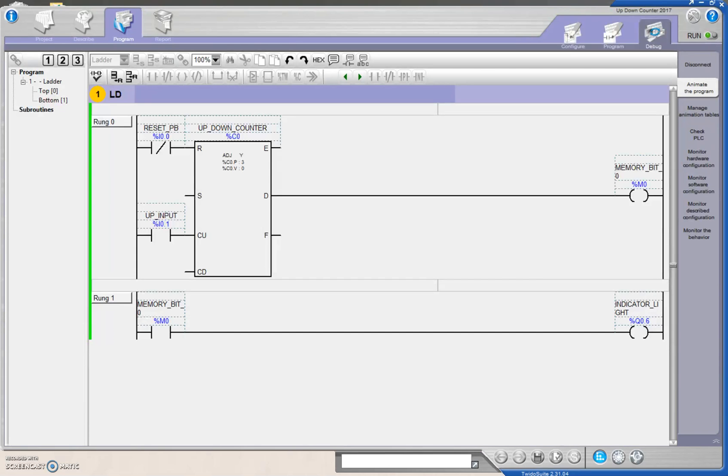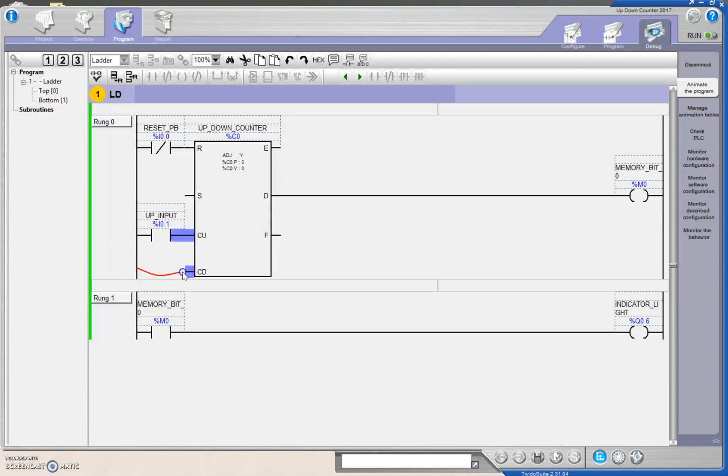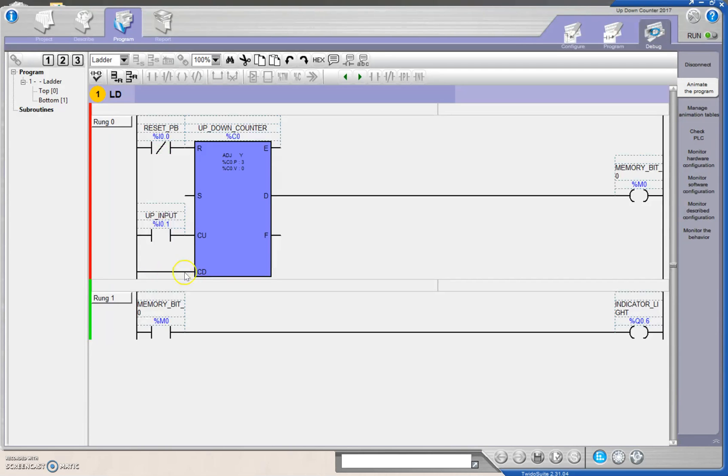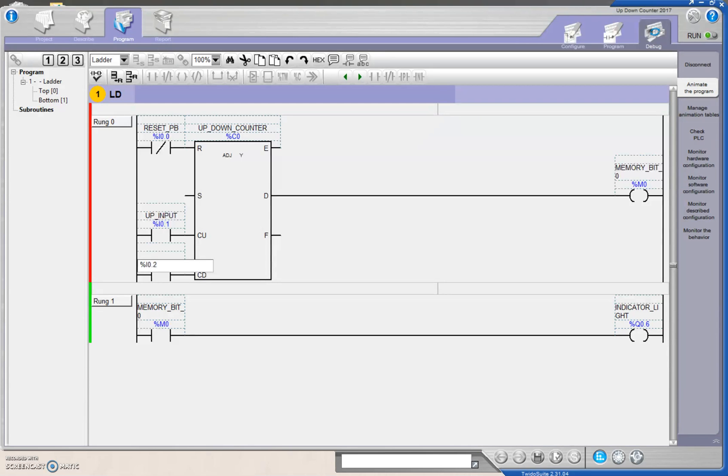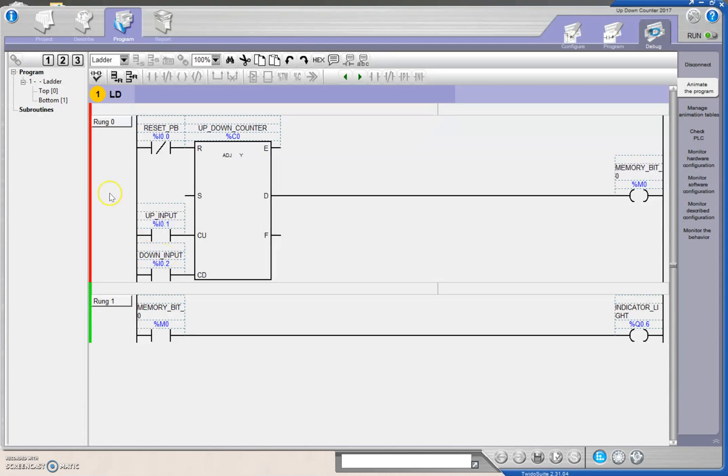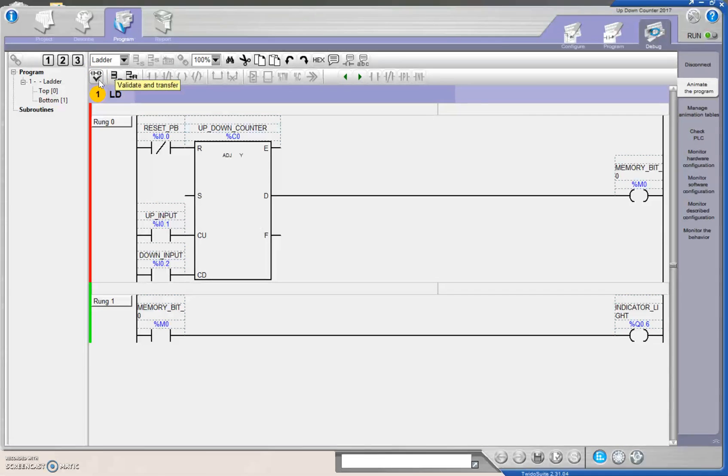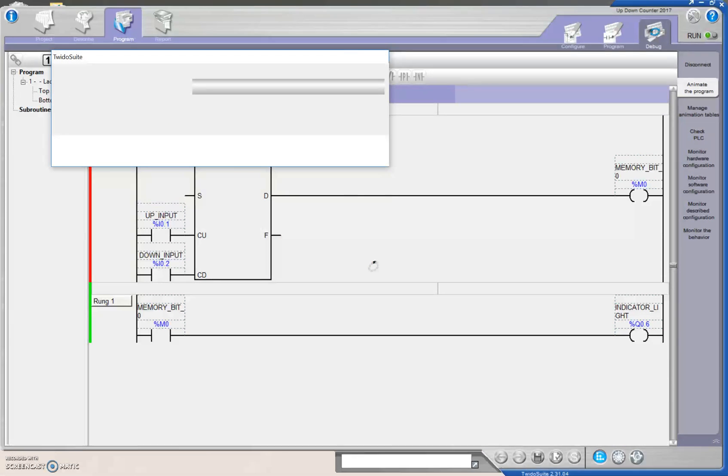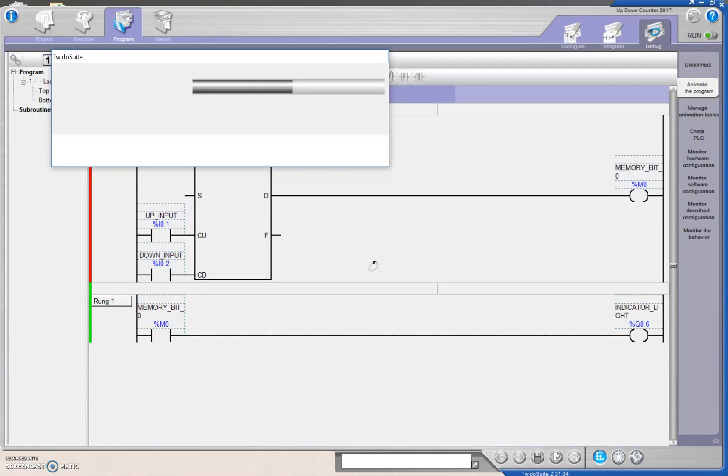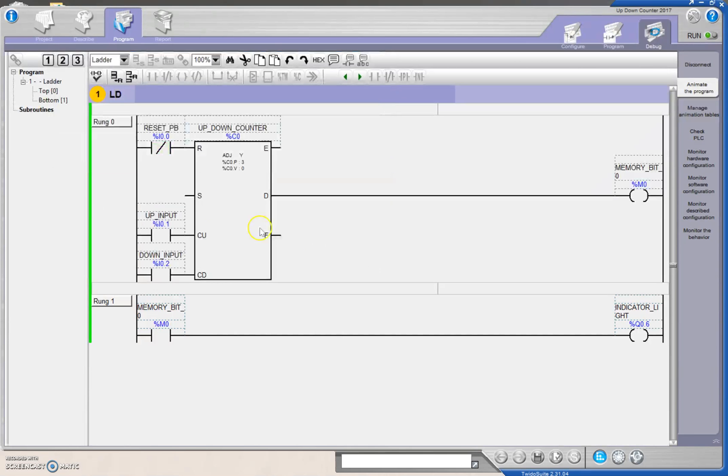So what I'm going to do now is I'm going to drop in another input here. Let's see if we can do this while the PLC is actually running. I'm going to grab this rung right here, bring it over until I see green, and I'll put an input there for my countdown. I'm going to select that rung right there and drop in an examine if closed because I'm going to use a normally open push button. And I'm going to label that guy input 0.2 and that I've already labeled as my down input. Now, this red right here is telling me that the PLC has absolutely no idea what I'm doing right now. So what I need to do is I need to go up here, validate and transfer. So it's going to check that everything's cool and then transfer that back to the PLC. Now we see the green, and now we're good to go.